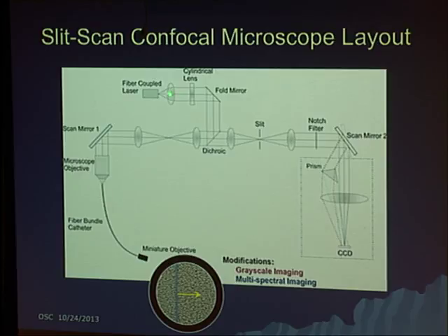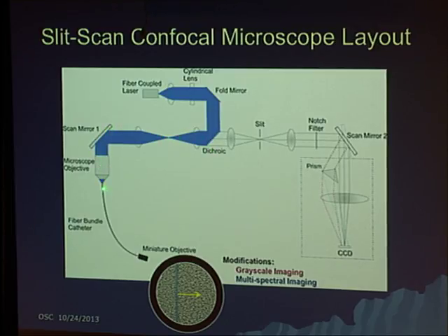So here's a lens system. The illumination looks something like this. It goes off of the dichroic beam splitter, focuses down off the scan mirror, and is focused onto the input. That would produce a point of light, except for a cylindrical lens here in the other orientation, in the direction out of the plane, blurs that in the vertical direction, so you get a line illumination rather than a point illumination. And this scan mirror then only has to scan one orientation to scan that line across.